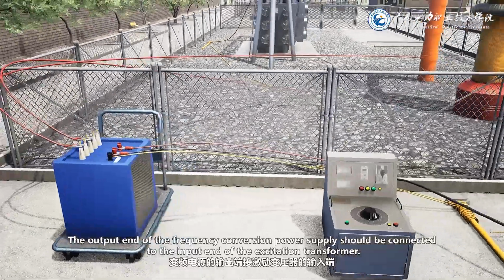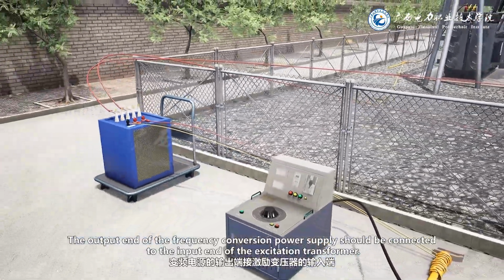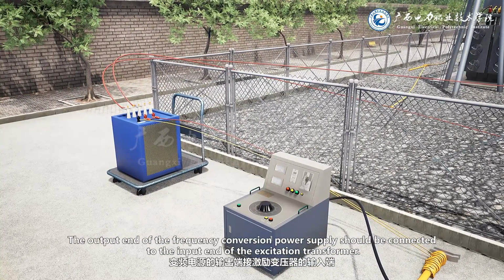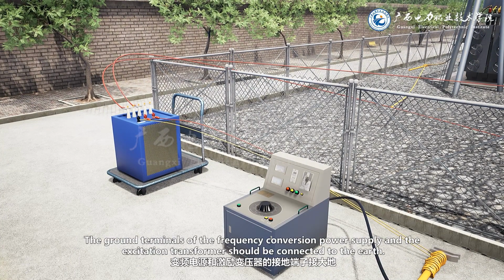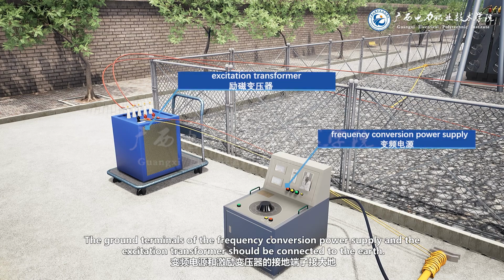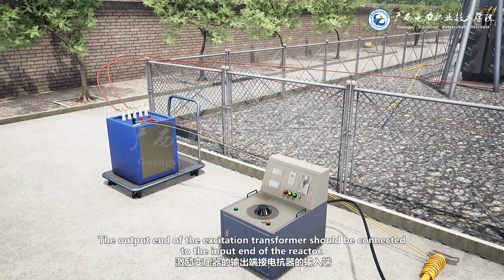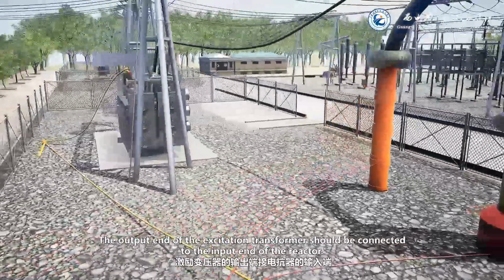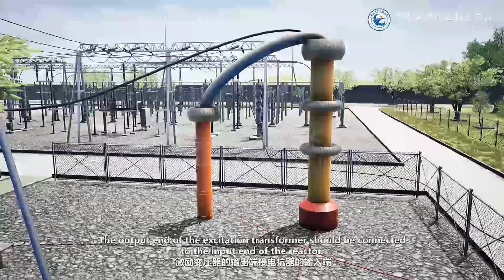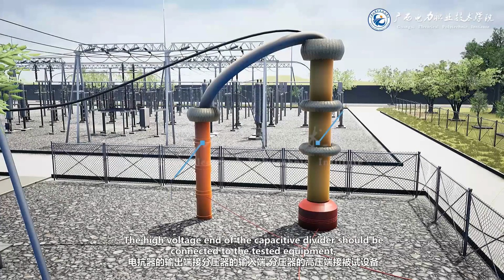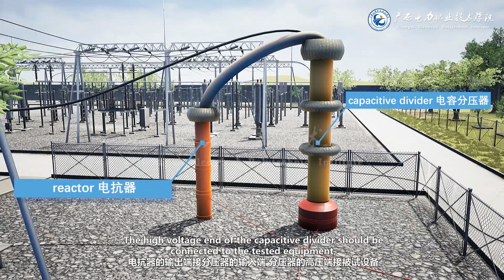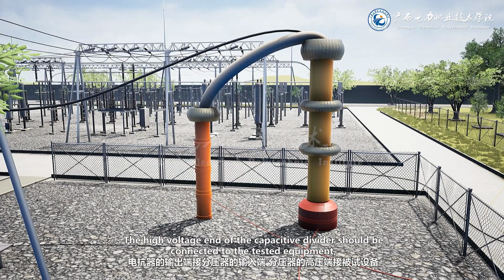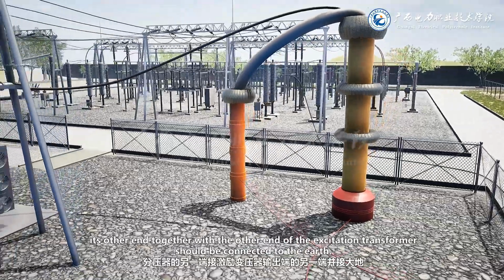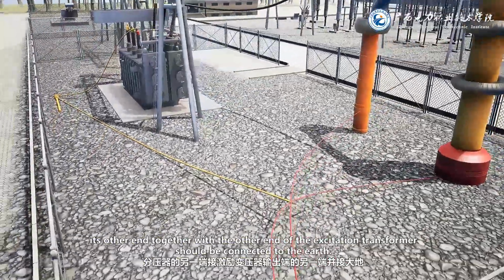The output end of the frequency conversion power supply should be connected to the input end of the excitation transformer. The ground terminals of the frequency conversion power supply and the excitation transformer should be connected to the earth. The output end of the excitation transformer should be connected to the input end of the reactor. The high voltage end of the capacitive divider should be connected to the tested equipment, and its other end together with the other end of the excitation transformer should be connected to the earth.